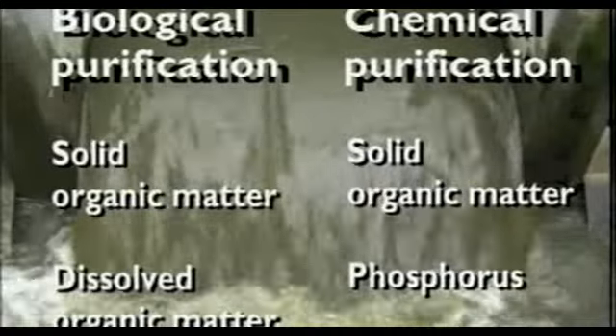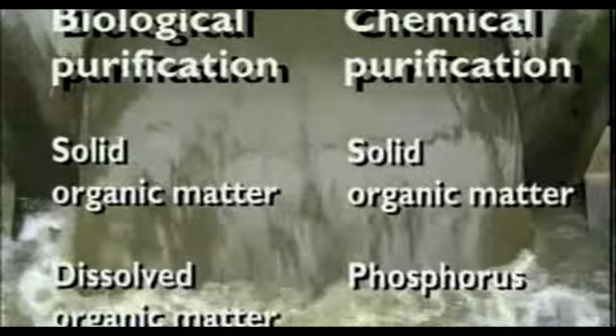Biological purification lasts a comparatively long time and is dependent upon the effectiveness of the microorganisms. Chemical and biological treatment work in different ways and achieve different results. The biological process removes both dissolved and solid organic matter. The chemical process removes solid organic matter and phosphorus. We have to determine the major causes of oxygen deficiency in waters and select the treatment process in accordance with local environmental requirements.